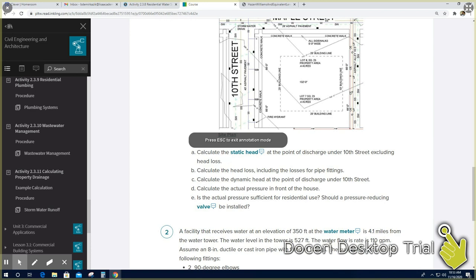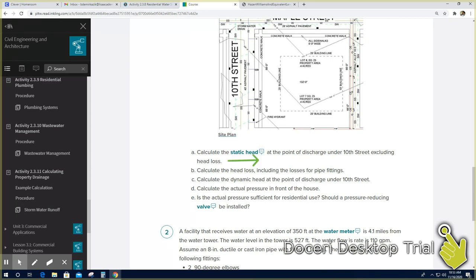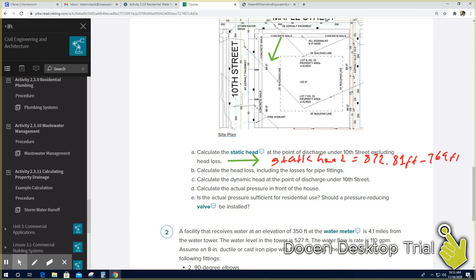Let's start with question A: calculate the static head. The formula is static head equals elevation of the water tower minus elevation of the site. The water tower elevation is given as 872.81 feet. From the graph, the site elevation is 769 feet. Subtracting them gives 103.81 feet — that's the answer for A.